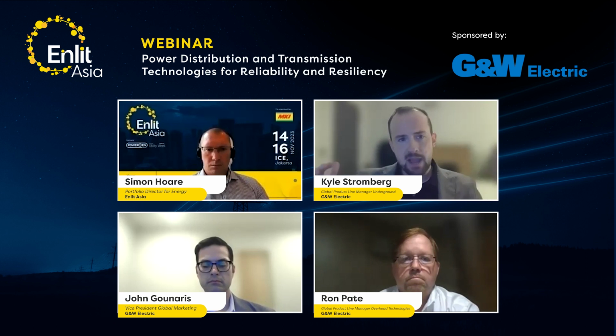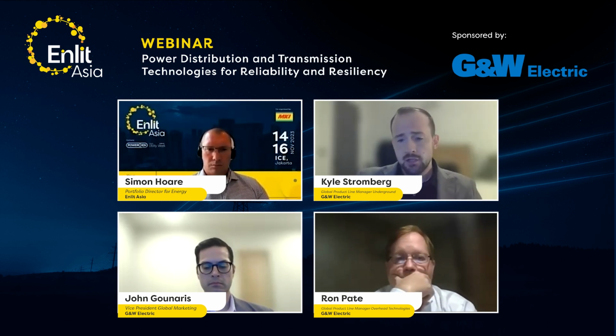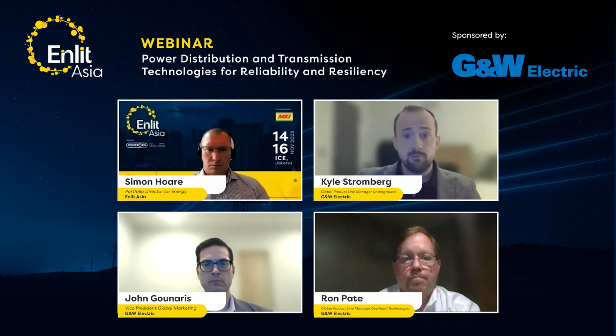If we step away from the apparatus and think about the system, some trends we've seen that support hardening are increased automation—moving away from a traditional manually operated switchgear approach to adding sensors for voltage, current, and position indication, paired with motor actuators or magnetic actuators capable of operating equipment without a human being at the site.